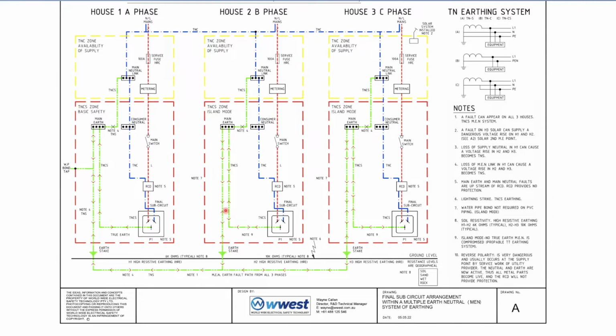See the arrows going up, and if you've got surge protection down here, or up here, or up here, they're just varistors. They're just going to pop, and that's going to drag in, and you're just going to get a super overload and a brownout. It's going to be like a bad situation. So anything to do with your lightning should have a separate true earth connection, not connected to your PE earthing system.